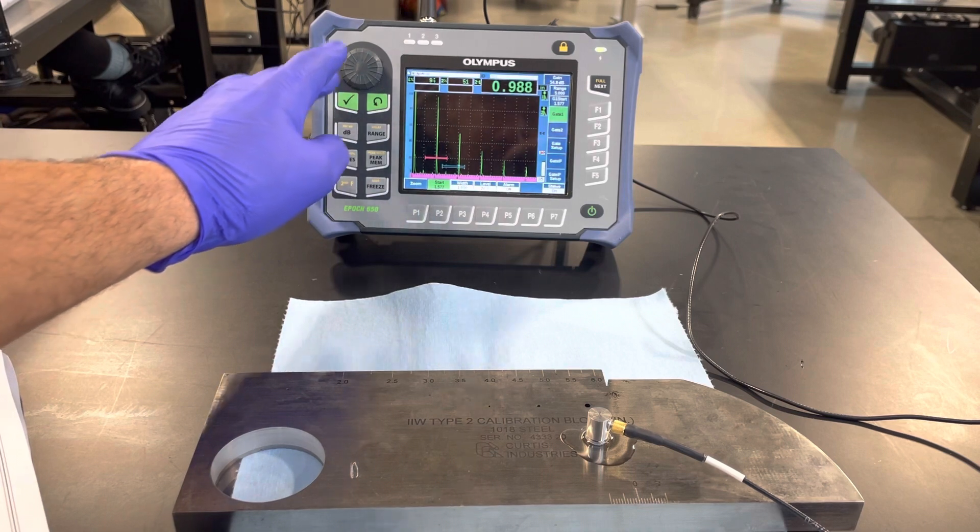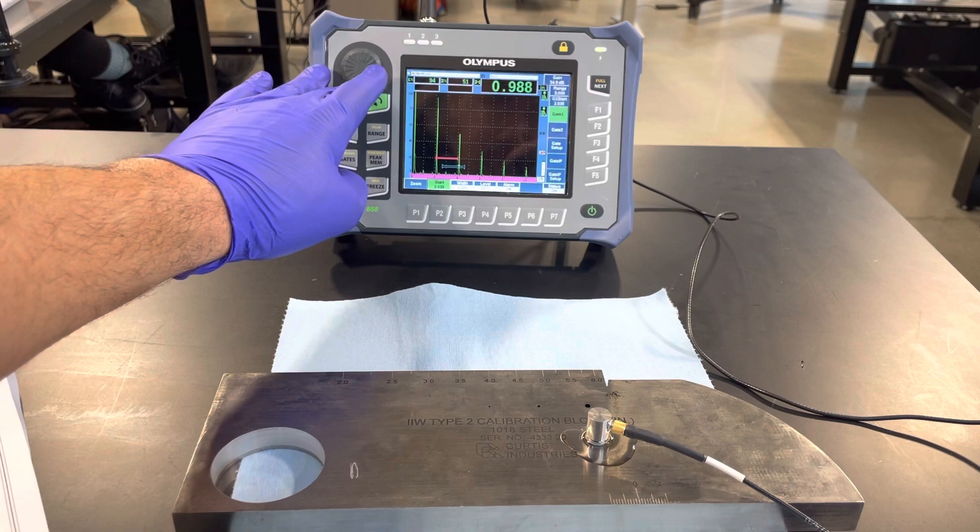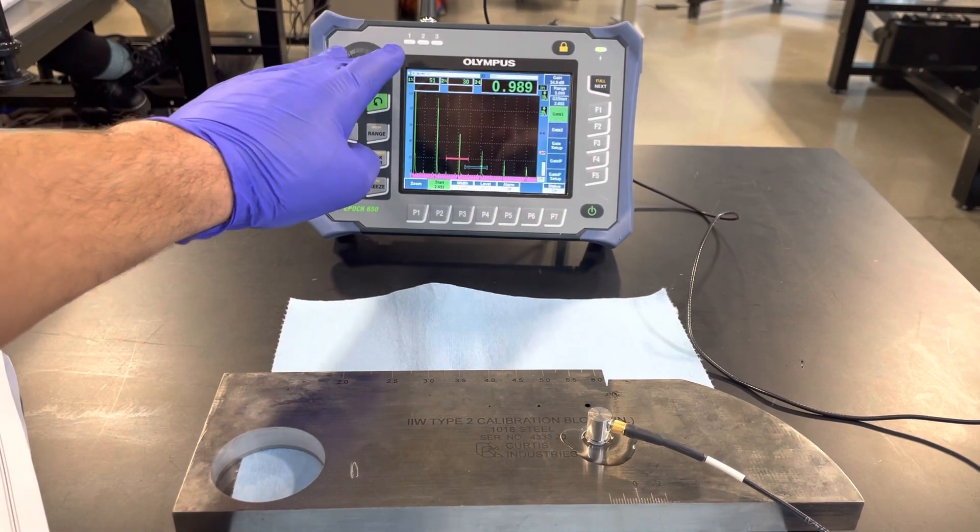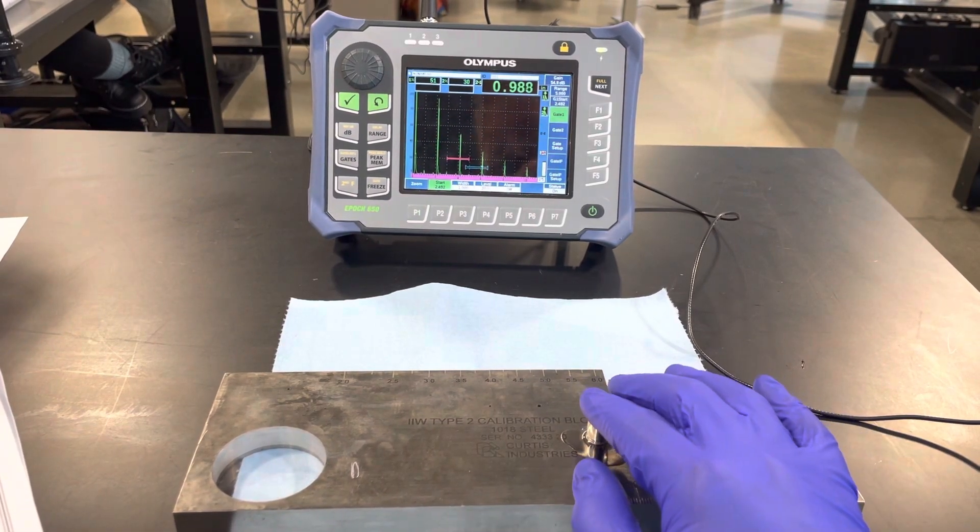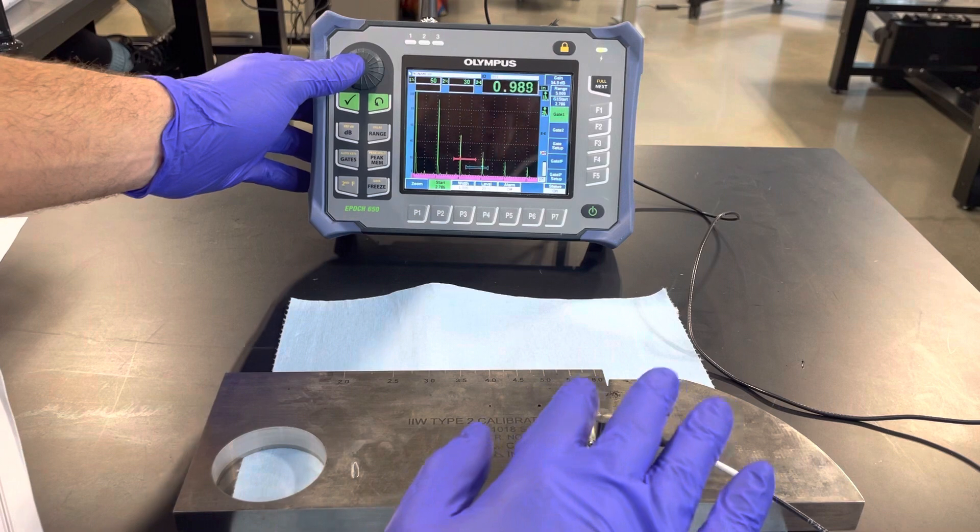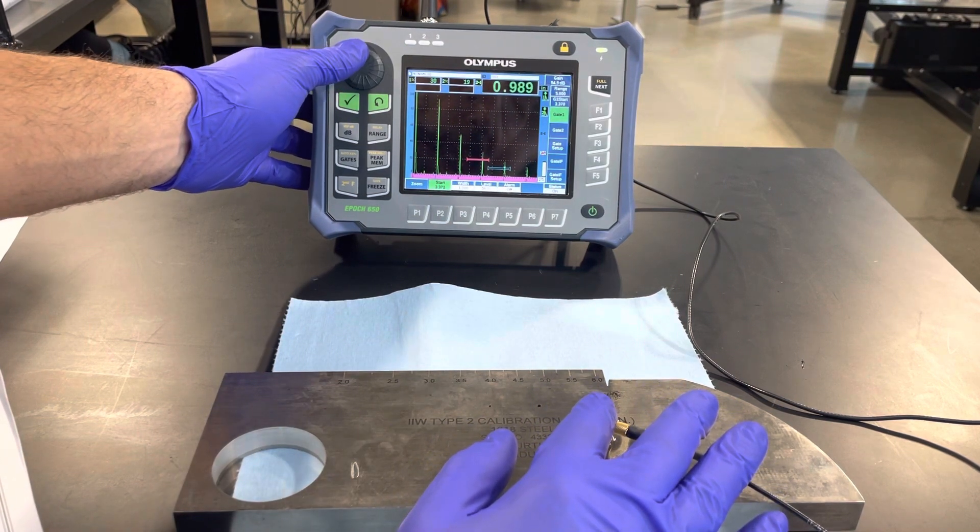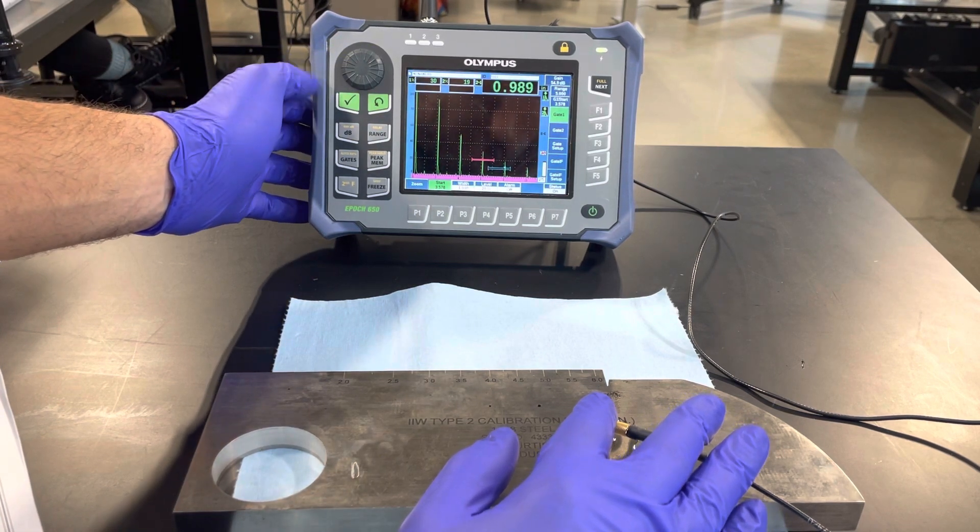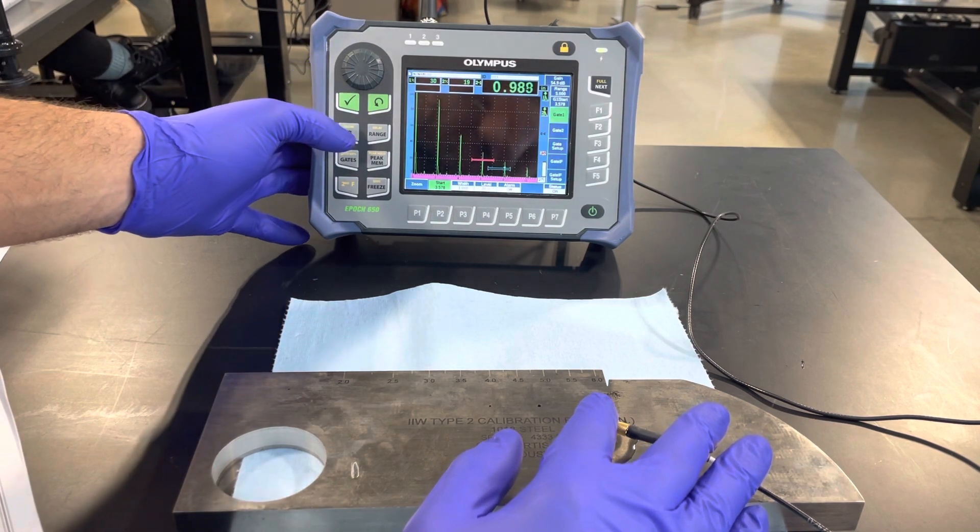We're going to run with the same 0.988 for the next one. Yep. We're at about the same 0.989. So I would say this unit is calibrated for horizontal linearity.